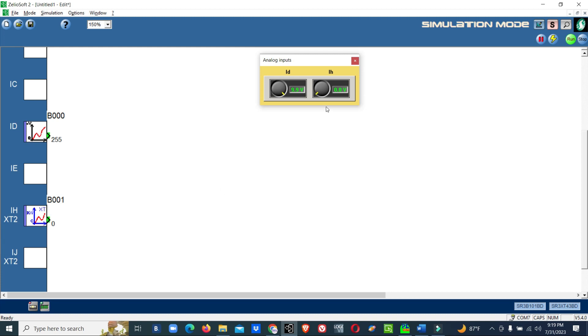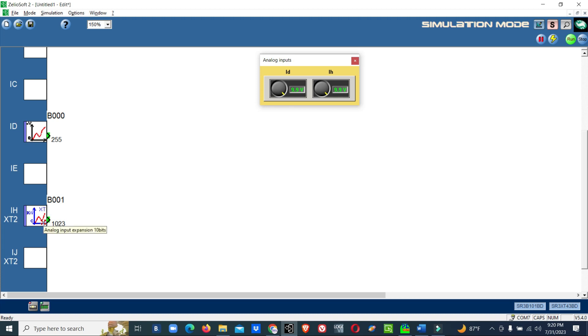Now for the 10-bit analog input — the same 0 to 10 volts is given from the field to the PLC, but the value shown is 1023. So from 0 to 10 volts, the binary value goes from 0 to 1023 for a 10-bit input. For 8-bit it is 0 to 255; for 10-bit it is 0 to 1023. Next we will see the 12-bit analog input.